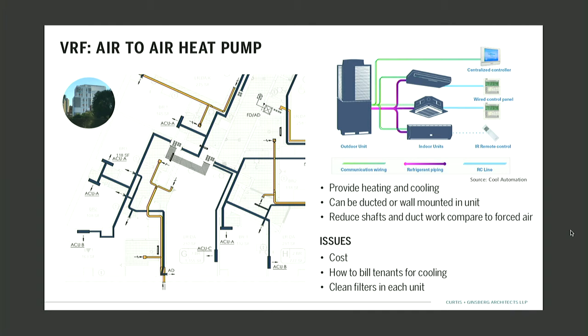Next. So we've used 3 different heating and cooling systems in our passive house. The first 3 we're using VRF, and those were all done. Each apartment had its own unit. You can put a unit on a wall, which looks sort of like an air conditioner. The problem is now the smallest one is 4,500 BTUs, and in a bedroom you only need 2,000. And it gets complicated. So the other way to do it is to put a unit mounted in the ceiling and duct to the rooms. So we were putting a wall-mounted one in studios and the ducted ones in 1s, 2s, and 3s. However, the issue always becomes, we'll talk about ERVs, you've got ERV ductwork, you have the VRF ductwork, and then you have the sprinkler pipes. And you don't want to raise your floor-to-floor height because that's going to cost money, et cetera.